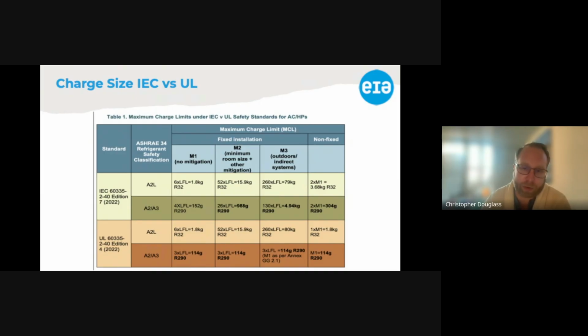So obviously the primary barrier here is the safety concerns. While IEC has approved these larger charge sizes for A2 and A3 refrigerants, they're already installed in Europe, Asia, and parts of South America. US standards and codes have to conduct and review their own research domestically, owing to some of that research not being public, in addition to differences with building code and equipment design, liability laws, and also just a general preference for more physical testing to confirm safety and mitigation methods.